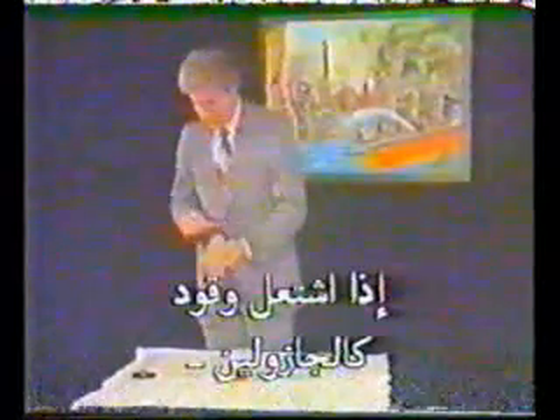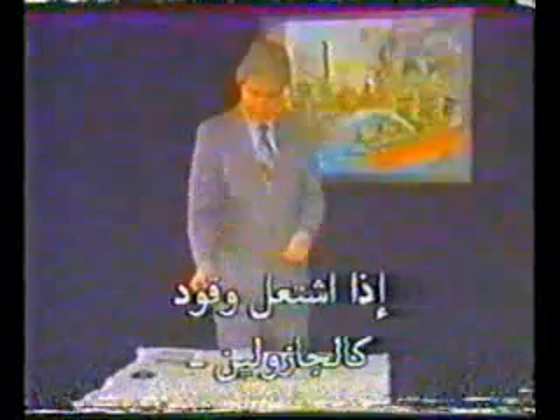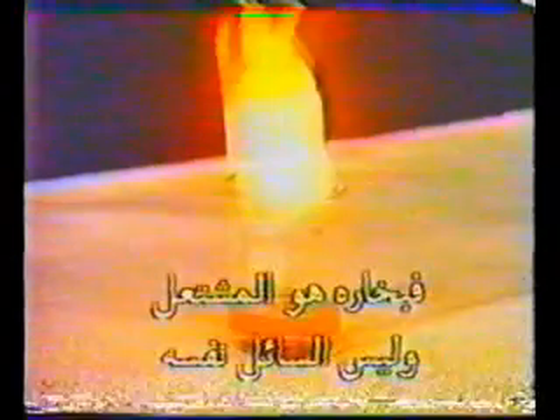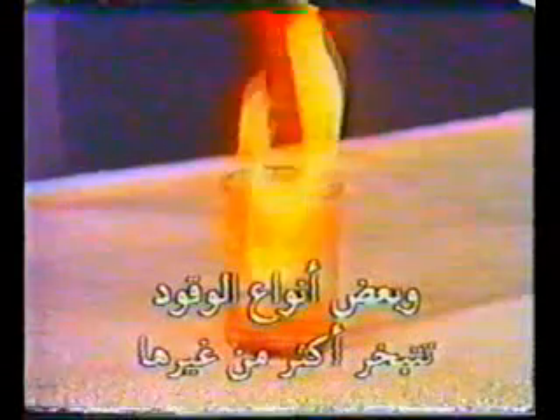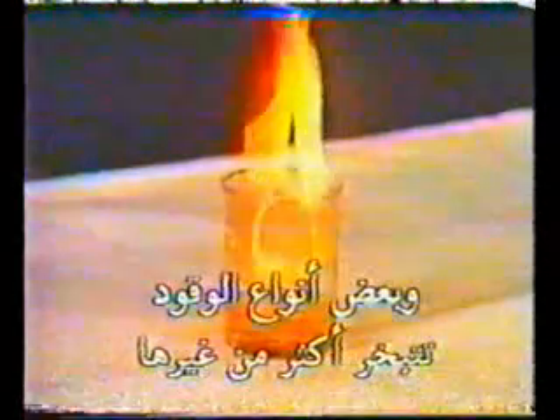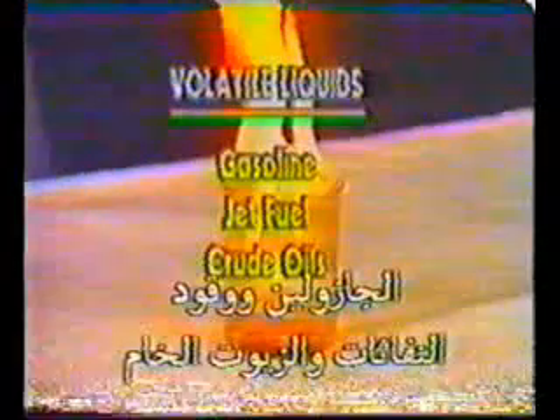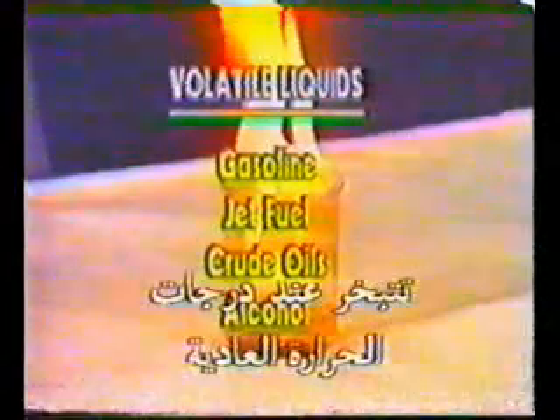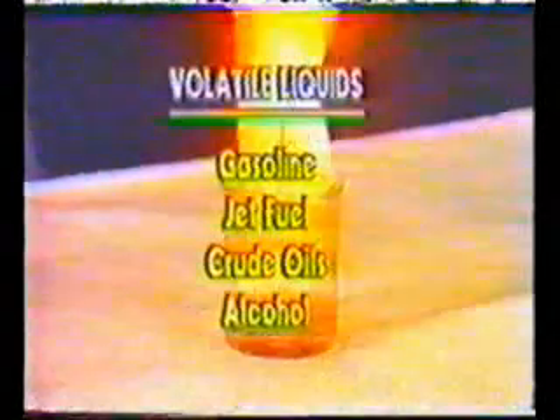If a Class B fuel like gasoline is ignited, it's the vapor and not the liquid which actually burns. This holds true for all flammable liquids. The fuel must be in a vapor state in order for combustion to occur. Some liquid fuels release flammable vapors more readily than others. Fuels like gasoline, jet fuel, some crude oils, and alcohol will readily vaporize at ordinary temperatures. These types of fuels are considered volatile liquids.